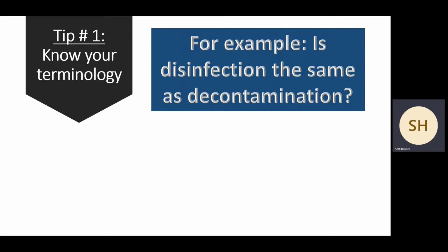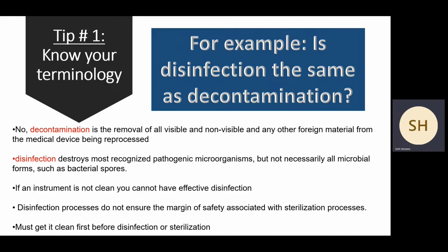Know your terminology. Okay, so I have a question for you. Is disinfection the same as decontamination? Well, I hope that your answer is no, right? Because decontamination is considered the removal of all visible and non-visible and any other foreign material from the device being processed. Okay, fine. That's really cleaning. That's what that is. Disinfection, on the other hand, destroys most recognized pathogenic microorganisms, but not necessarily all microbial forms of life, such as bacterial spores. So that's why disinfection is good, but sterilization, as we'll talk about, has a higher margin of safety, right? That's that middle bullet point there.